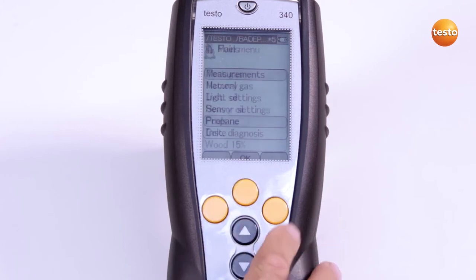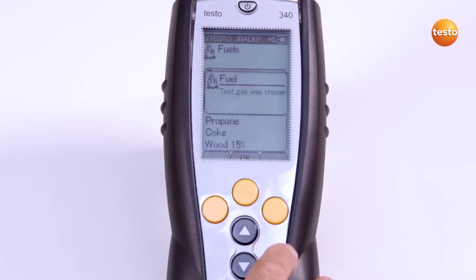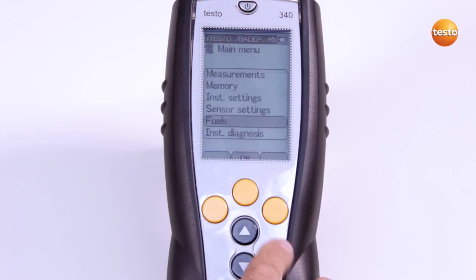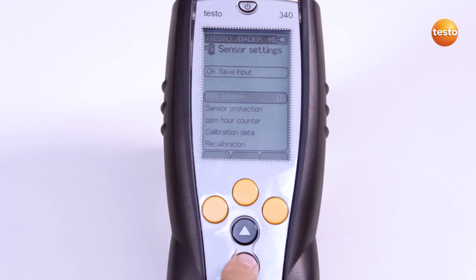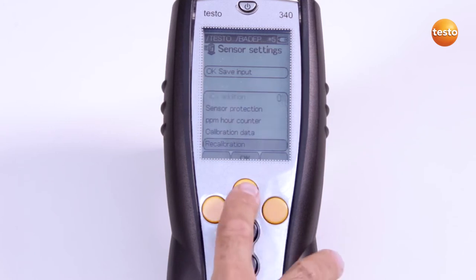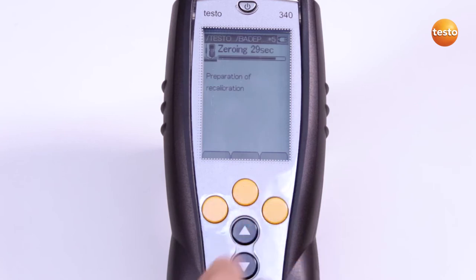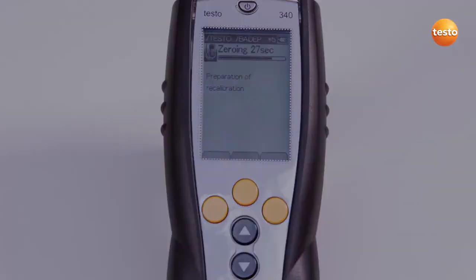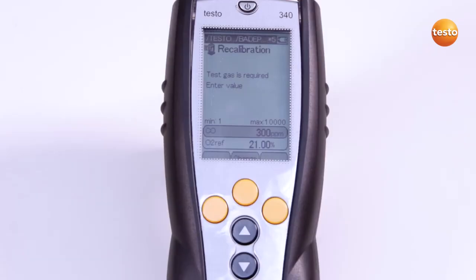First, I select Test Gas in the Fuels menu. In the main menu, I select Sensor Settings and Recalibration. Automatic zeroing is now carried out. Now I select the sensor for the recalibration and enter the required value.